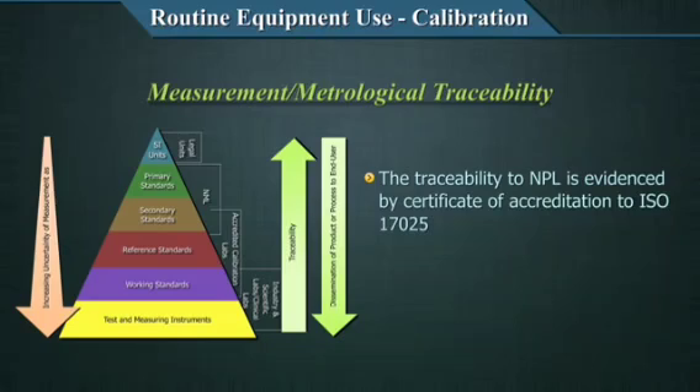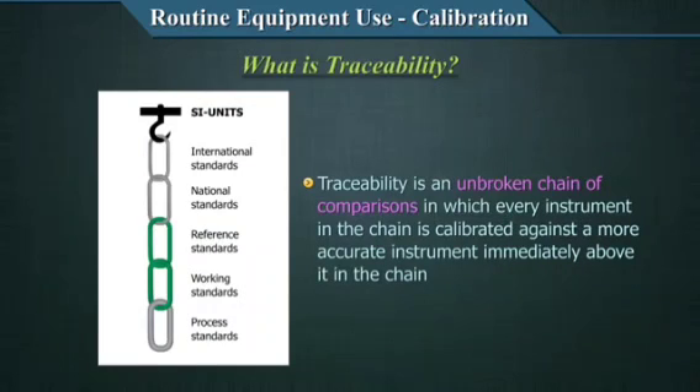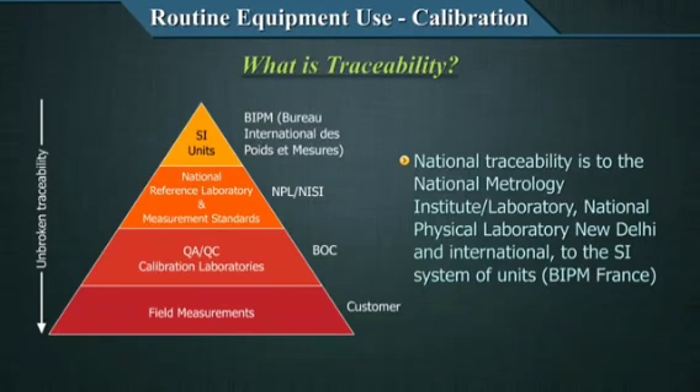To reiterate once again: traceability is an unbroken chain of comparisons in which every instrument in the chain is calibrated against a more accurate instrument immediately above it in the chain. Calibration is the linking of measurement standards and measuring instruments to relevant national or international standards through an unbroken chain of comparisons. National traceability is to the National Metrology Institute or Laboratory — NPL, New Delhi — and international traceability is to the SI system of units at BIPM, France.